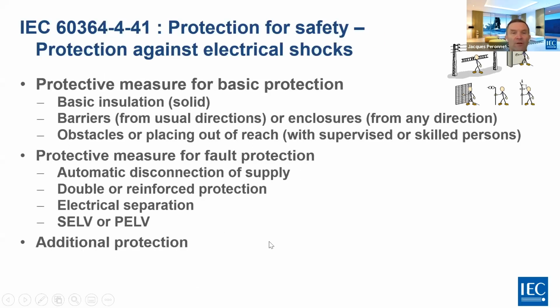Regarding the protection for safety, which is the protection against electric shock, this is the IEC 60364-4-41. We are going to describe in this document how to make the protective measure for the basic protection. So it could be made by basic insulation, so it's solid. It could be made by barriers from the usual direction or enclosure for any direction, or it could also be done by obstacle or placing out of reach. In this case, we require that the installation is supervised by skilled people.